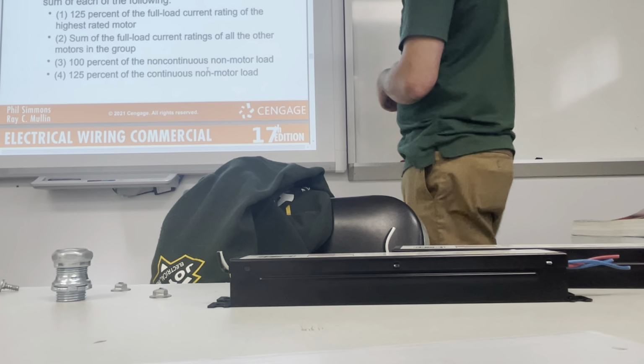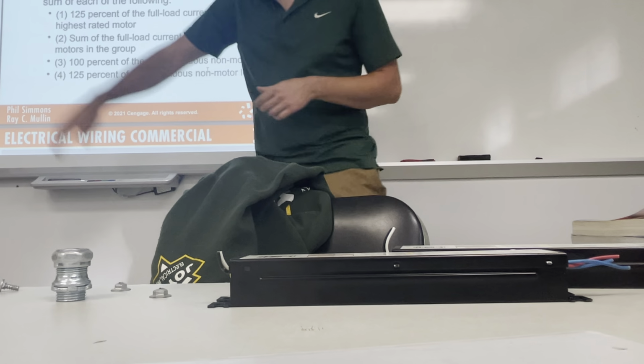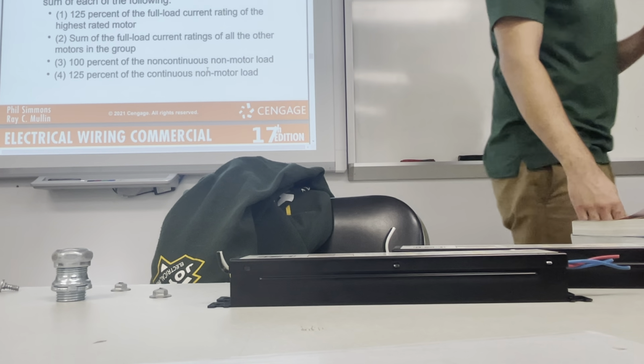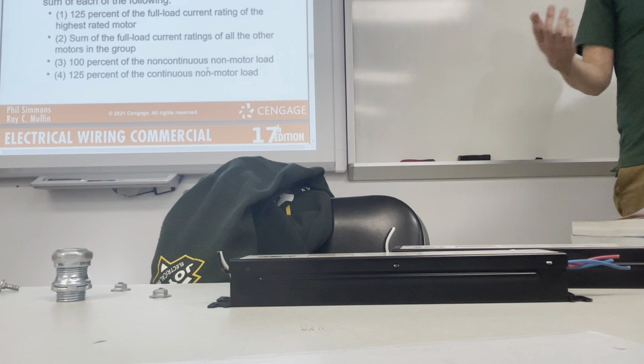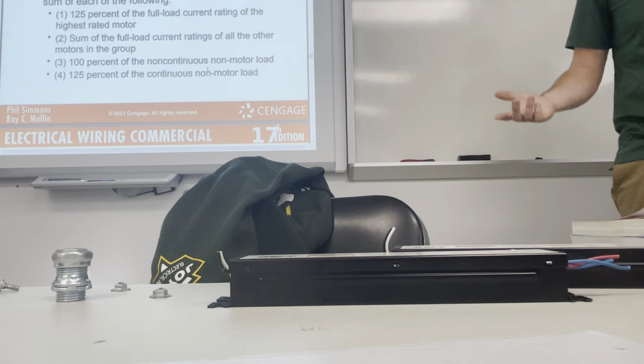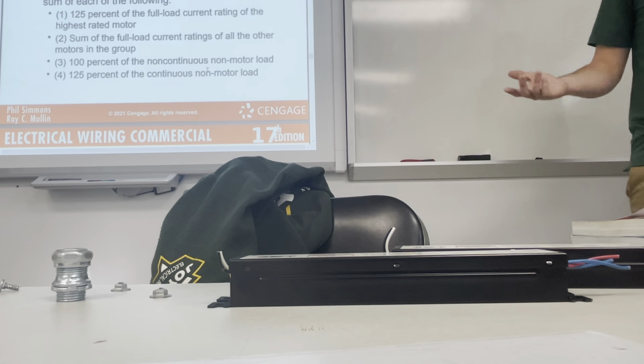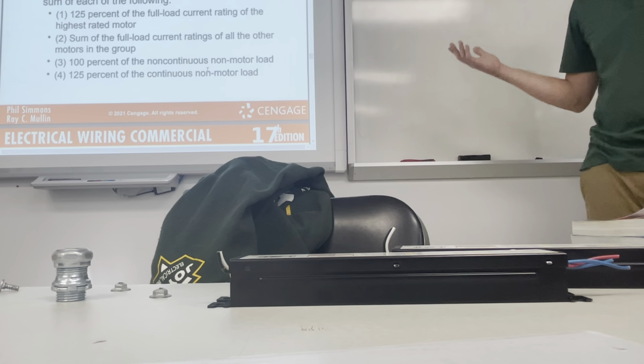So for this situation, they're just saying that if you are going to supply multiple motors off the same circuit, it had best be ready to handle all motors running at their full bore, right? Is that hard to digest there? Okay. So if you have two motors pulling 60 amps, you don't want to have it on an 80 amp breaker or run it with 6-gauge wire. You know what I mean? It's got to be able to handle both motors on with their full current.